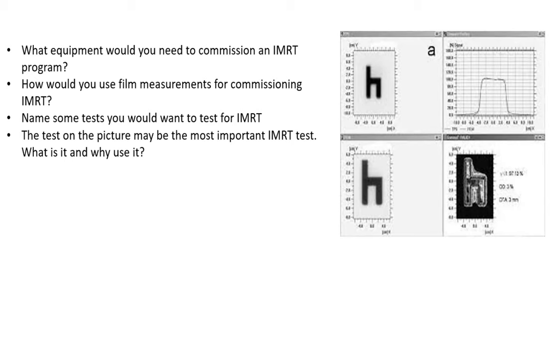As usual, we will always reference a task group when we can, and TG-119 is the perfect reference for IMRT. For equipment, you want a water-equivalent phantom — you want to scan that with a CT and allow it to be used within the treatment planning system.